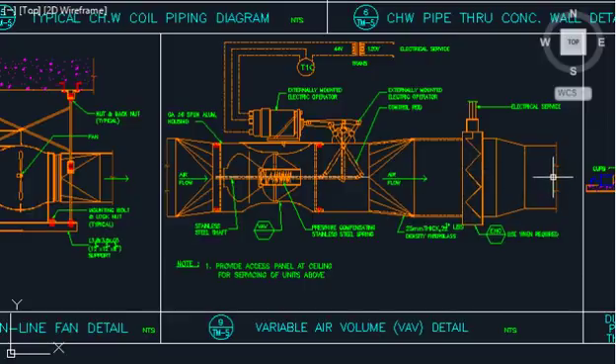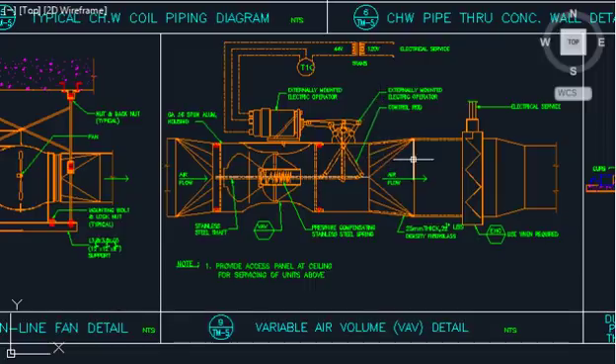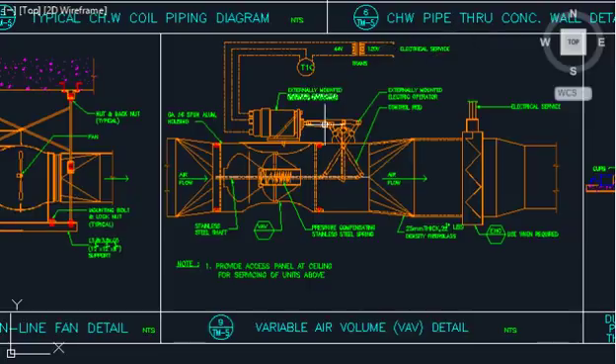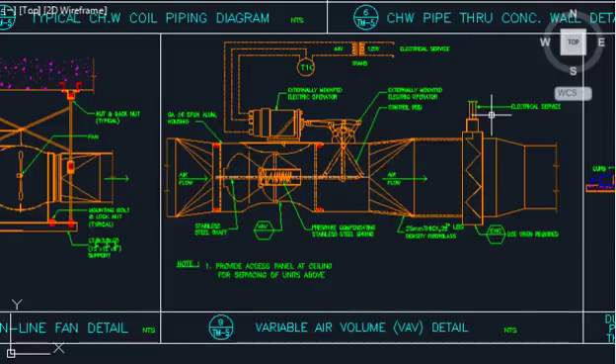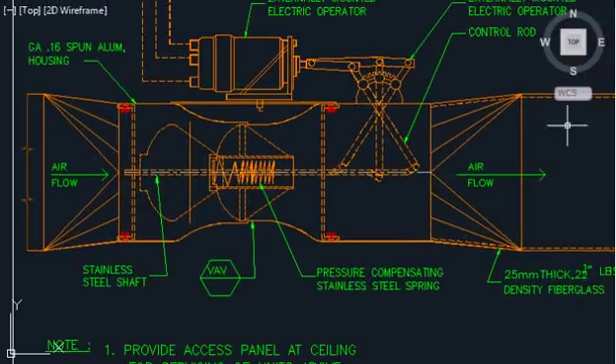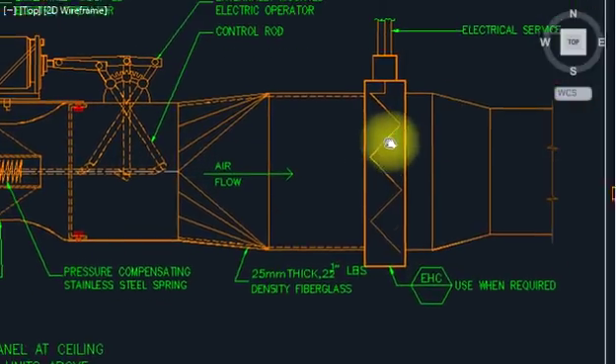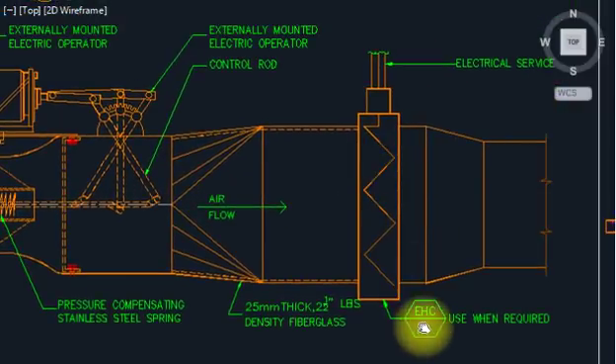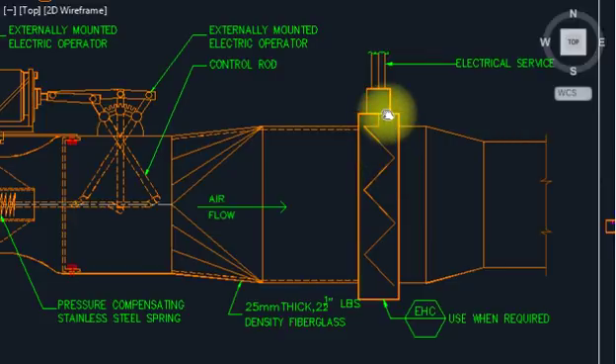If you want to close the AC in just this room, you cannot do that directly because the AHU serves all rooms — closing it shuts down the whole system for all rooms. But if we have installed a VAV, we can shut down just this room using the thermostat. You can stop airflow or reduce the air via the thermostat.